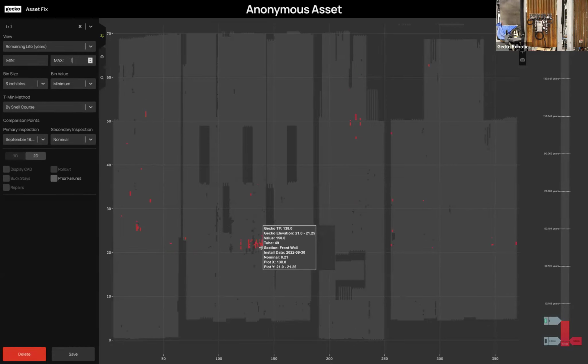So this is actually something we discussed with the plant. Take this area, for example - this is the area they didn't get any data on last year. But look at this, there's a bunch of red in this area. What the plant explained is they've been adjusting their airflow, and that changes both the location and amount of wear. This right here is turning out to be a very high airflow area. We've got a wing sticking out here, and there's a bunch of air being sucked up between them, creating a lot of erosion in this spot.